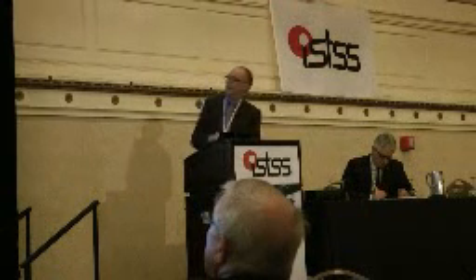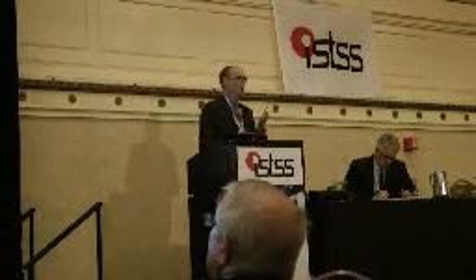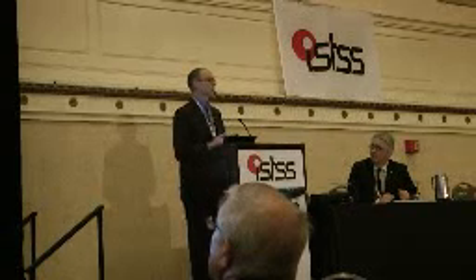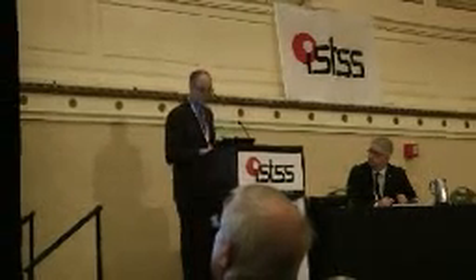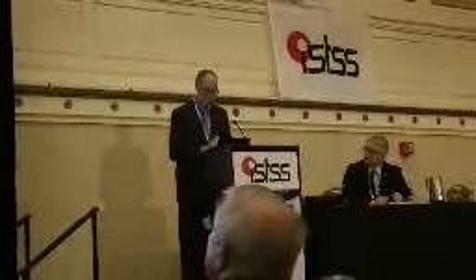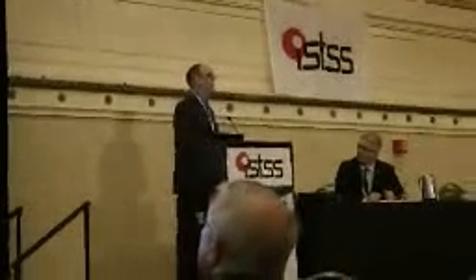Now, what do these systems look like? As I said, the active firefighting system has 4 major components. It's the deluge sprinkler system that was obvious already in the film you saw. A longitudinal ventilation system. I'll stick with ventilation if you don't mind. A temperature measurement system, and a control system that will act upon the temperature from the measurement system and will activate sprinkler and ventilation.